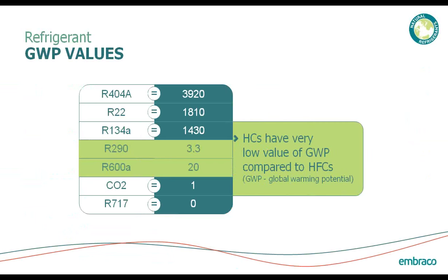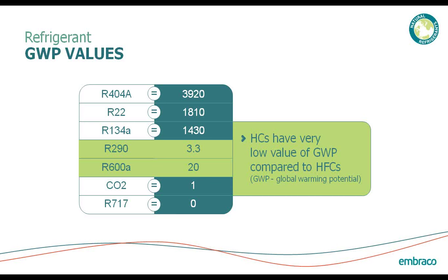Let's go into some GWP values. GWP is defined as the global warming potential relative to one pound of CO2, so one pound of CO2 equals one. Current commonly used refrigerants like R404A are close to 4,000 GWP per pound of refrigerant, and R134A is 1,430. Recent EPA legislation is going to be banning the use of those refrigerants by 2020 because of these high GWPs. One thing to consider is R290, which has a GWP of 3.3, and R600a, which has a GWP of 20 — very low values compared to the current HFC refrigerants being used.